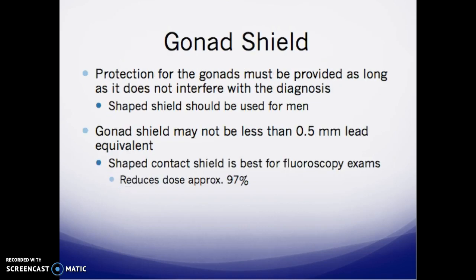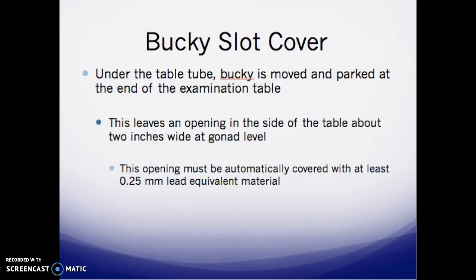Gonadal shields must be provided for protection of the gonads as long as they do not interfere with the diagnosis. Shape contact shields are used for men and must not be less than 0.5 millimeters of lead equivalent; they can reduce dose by up to 97% for men. Bucky slot covers: when the Bucky is moved and parked at the table end, it leaves an approximately 2-inch gap at gonad level that must be automatically covered with at least 0.25 millimeters of lead equivalent.